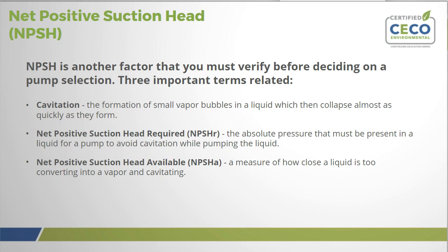When these vapor bubbles produced by cavitation collapse, they generate a huge amount of pressure at a very small point. When these vapor bubbles burst, it's basically like a super high pressure at a very concentrated point, and it creates significant damage inside the pump. Typically, you see cavitation on that leading edge of the impeller vanes, and it's very damaging. It's an erosive type of damage inside the pump. It affects the impeller and the casing. So NPSHR, I'm going to just flip to the next slide here.